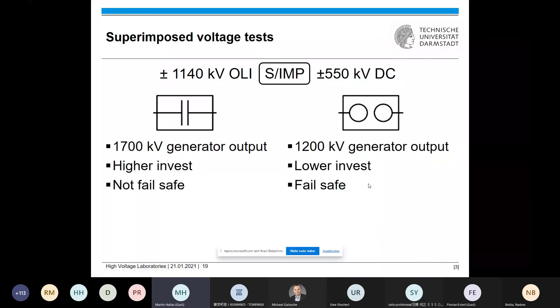And the spark gap actually really works, especially for oscillating impulse voltages. It works much better than for conventional testing. Here you see some oscillograms in our test facility for oscillating lightning impulse and switching impulse testing. You see you get a very smooth curve for the testing of bipolar and unipolar testing. And what else is interesting, that you also can achieve it, that you test 550 kV DC even with less than 2 times the DC voltage amplitude of a switching impulse voltage. This is also possible with this configuration.